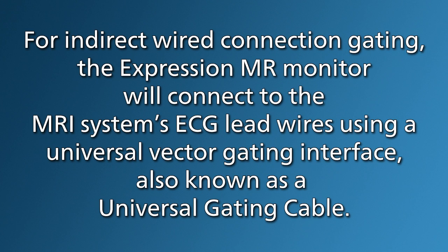For indirect wired connection gating, the Expression MR monitor will connect to the MRI system's ECG lead wires using a universal vector gating interface, also known as a universal gating cable.